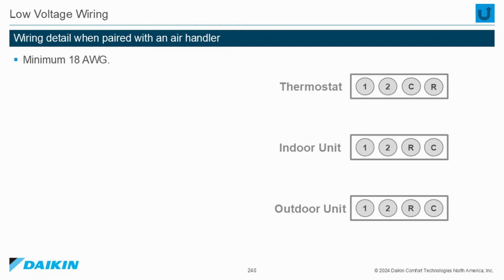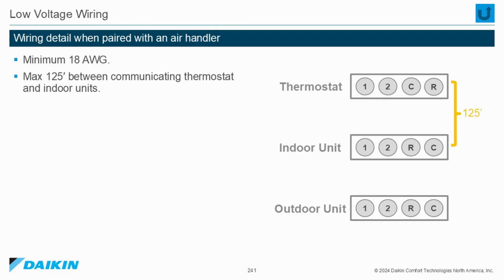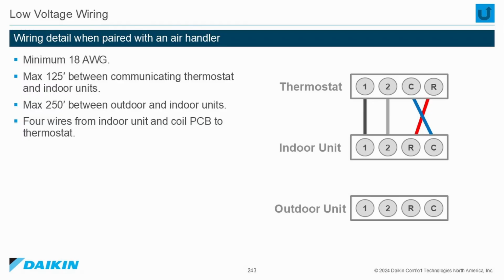Wiring detail when pairing with an air handler. Minimum of 18-gauge AWG. Maximum of 125 feet between communicating thermostat and indoor units. Maximum 250 feet between the outdoor unit and the indoor units. 4 wires from the indoor unit to the coil printed circuit board to the thermostat. 2 wires are required from the indoor unit to the outdoor unit.